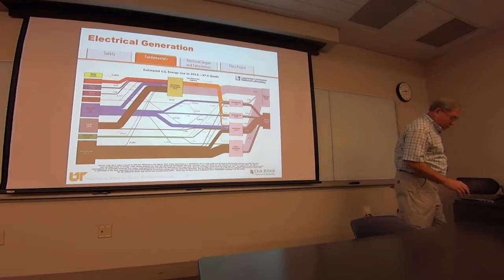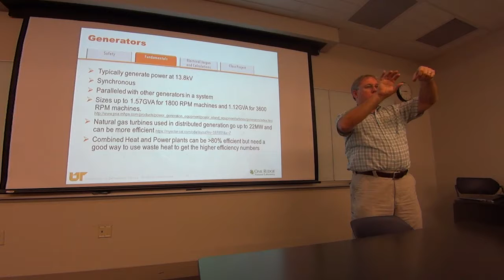Now, talking about generators: they typically generate power at about 13,000 volts because the wires are small and have to fit the windings. That voltage goes into a switch yard, a TVA substation or similar, gets stepped up to higher voltage, and is transmitted. They're synchronous—meaning to get a generator online you spin it up to speed, synchronize it with the utility, and close it in, and it stays at that speed. When you add more load, there's something called a torque curve, but the generator keeps spinning at the same speed.